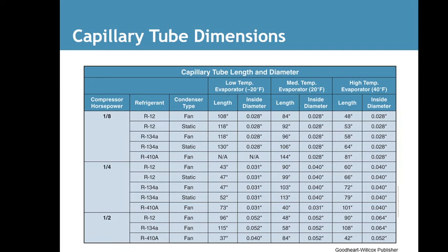Capillary tube sizing is a chart of dimensions, not something you probably ever use in your life, but you can. You're going to buy a unit that has capillary tubes already on it, or if you have to replace those capillary tubes, you can get the size that you need to change them out. But capillary tubes rarely get changed out. If you get a leak on one, you cut it off, and you braze it back on without that small little section.